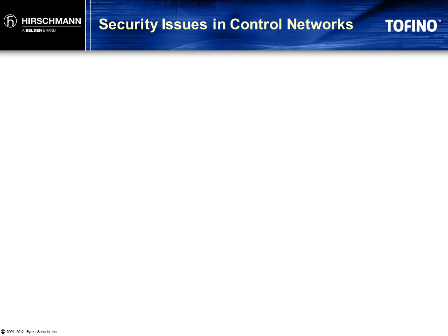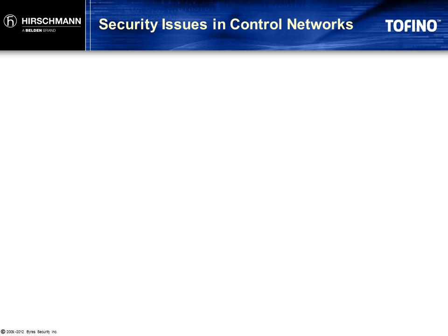Most cybersecurity issues fall into three major categories. First, control networks are full of what we would call soft targets — devices that are extremely vulnerable to disruption through their network interface. The PCs in many plants run for weeks or months without any security updates, and some even operate without any antivirus tools. In addition, many of the controllers in these networks were designed in an era when cybersecurity was not a concern. As a result, many of these devices can be disrupted by malformed network traffic or even by high volumes of correctly formed traffic.